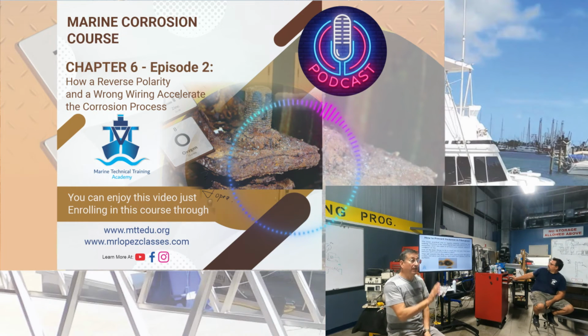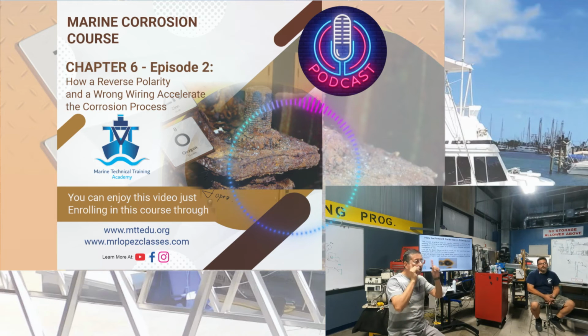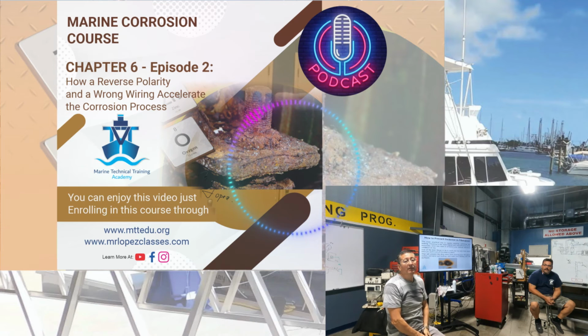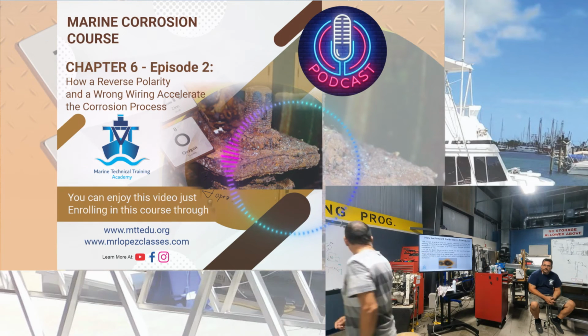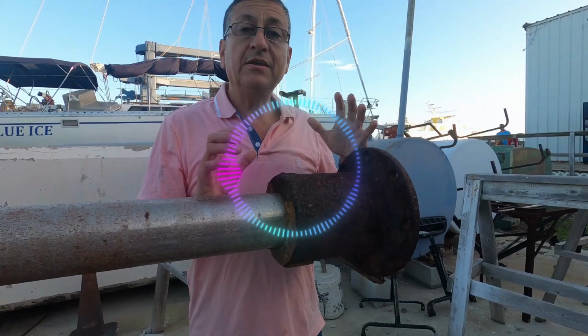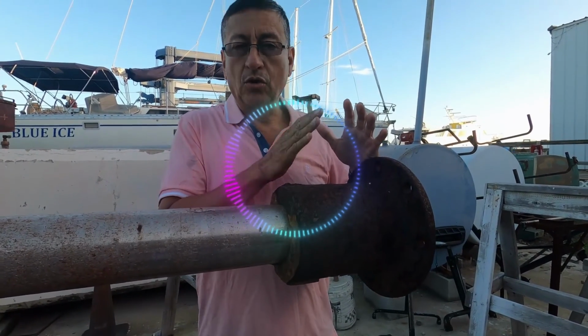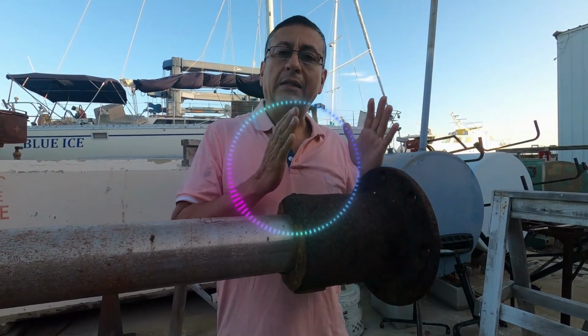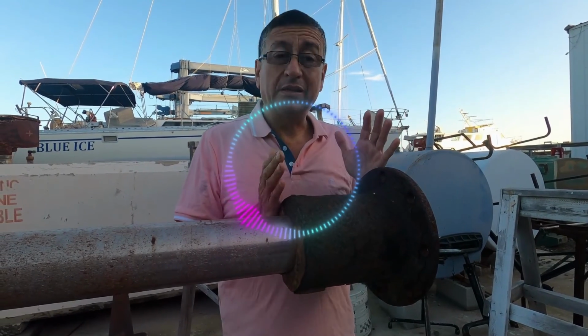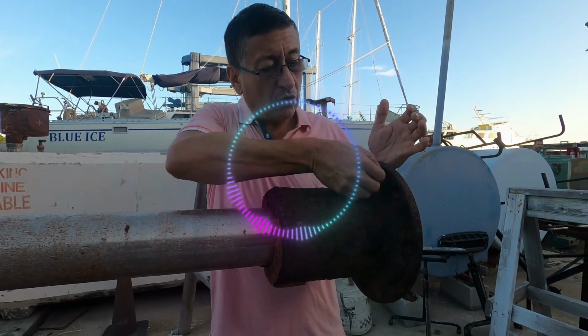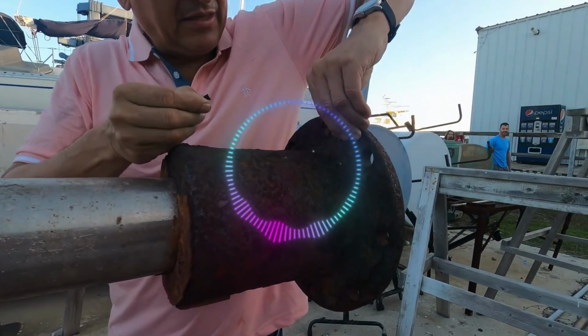The light is on because it's receiving power. What is the meaning of that? The green light is on because my polarity is correct. What happens if the reverse polarity light is on? If the red light for reverse polarity is solid, it's because I switched the hot and the neutral on the panel. I connected the hot to the neutral bus bar, and the neutral is on the breakers. What happens in that case?